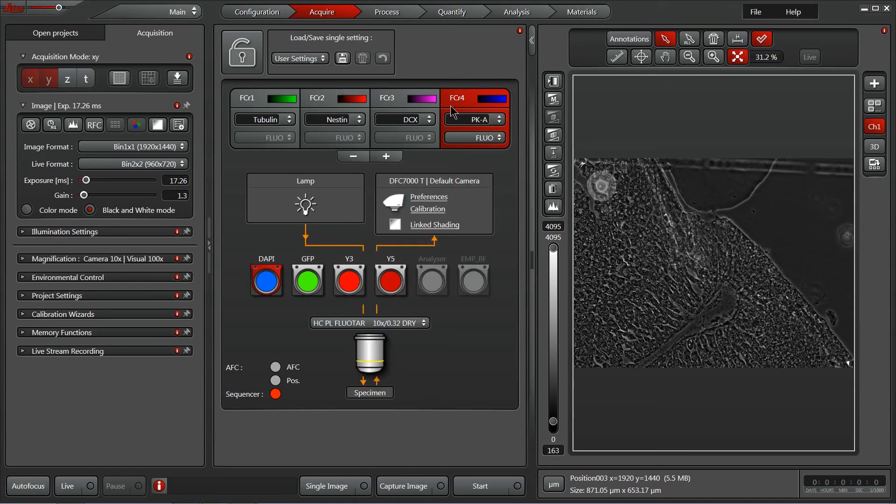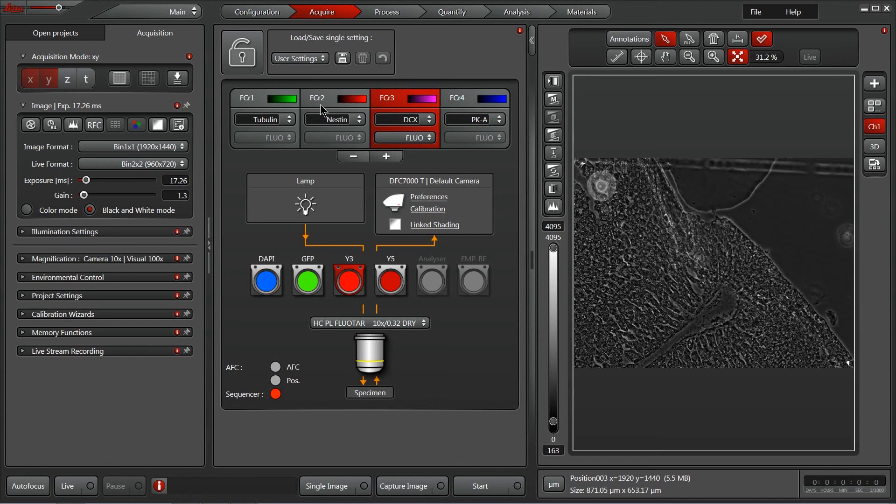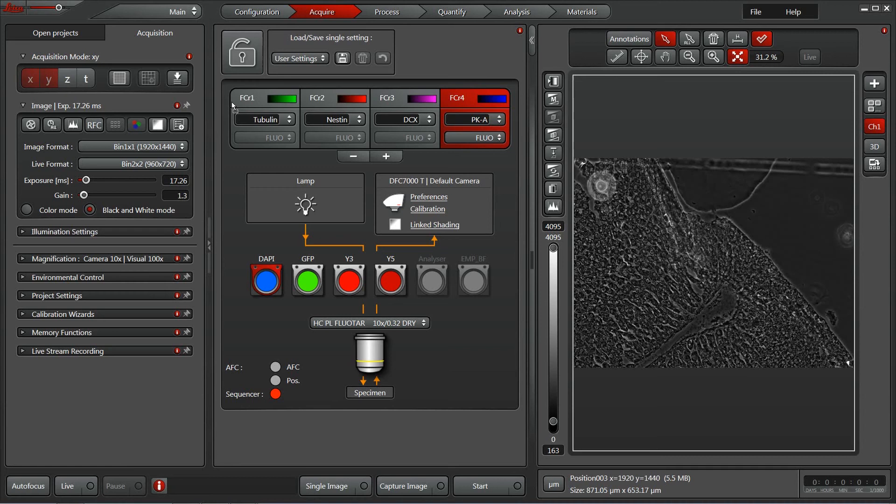Awesome. So now I've got four fluorescence channels set up. Each of these can be customized with different exposure times and illumination settings. If you prefer to do your DAPI first, you can simply select that cube, click on it, drag it to the position you'd like, and it'll reassign the order, keeping all the information consistent.